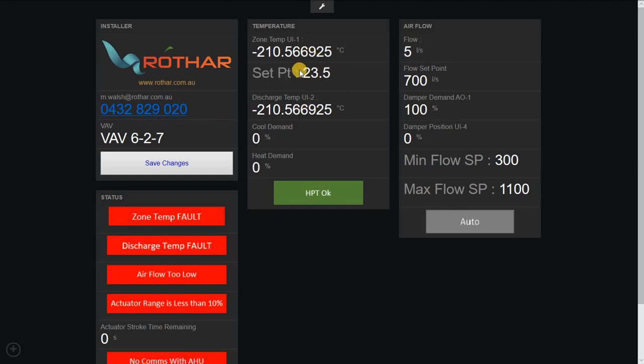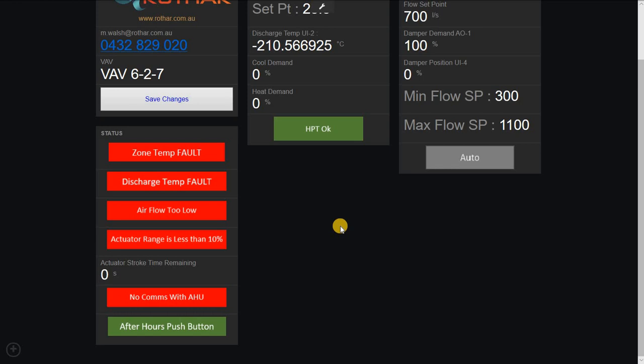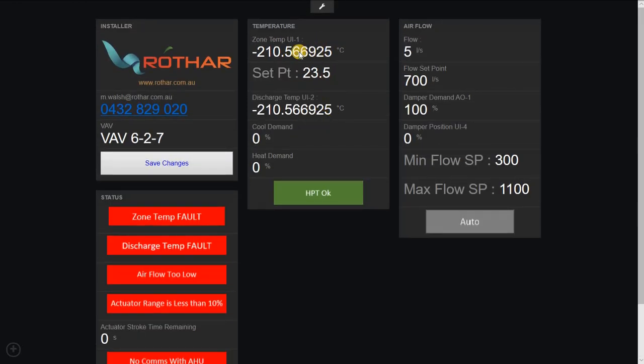You can change the set point from here, the zone set point. You can also change the min and max flow set points, as well as see other things that the tech would want to see from an overview perspective when you're commissioning the VAV. Are the temperatures okay? Is it communicating? Are the temperature sensors okay, which I think I've said already? Is it controlling? What's our damper position, the demand and the feedback?